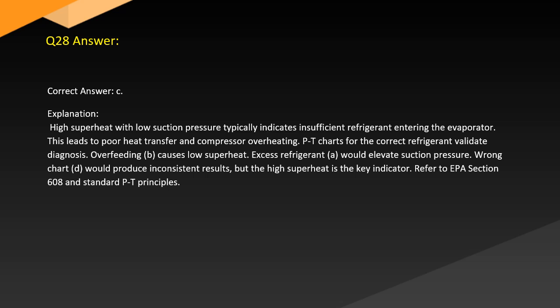Answer. Correct answer: C. Explanation. High superheat with low suction pressure typically indicates insufficient refrigerant entering the evaporator. This leads to poor heat transfer and compressor overheating. PT charts for the correct refrigerant validate the diagnosis. Overfeeding, B, causes low superheat. Excess refrigerant, A, would elevate suction pressure. Wrong chart, D, would produce inconsistent results, but the high superheat is the key indicator. Refer to EPA Section 608 and standard PT principles.